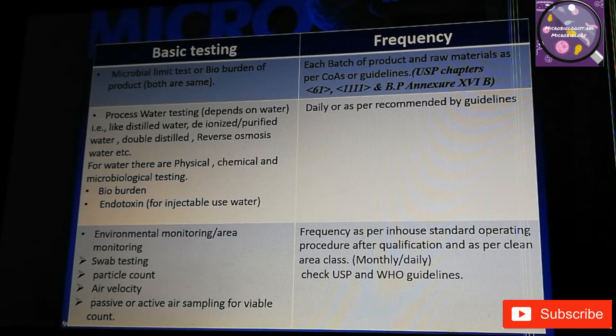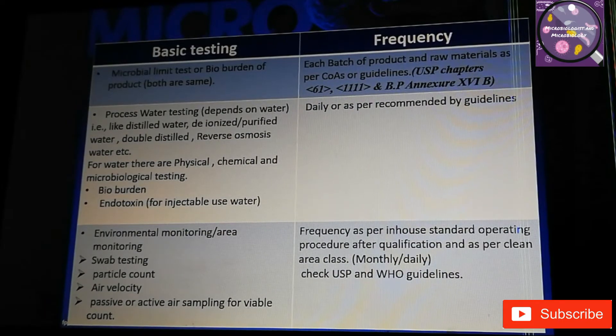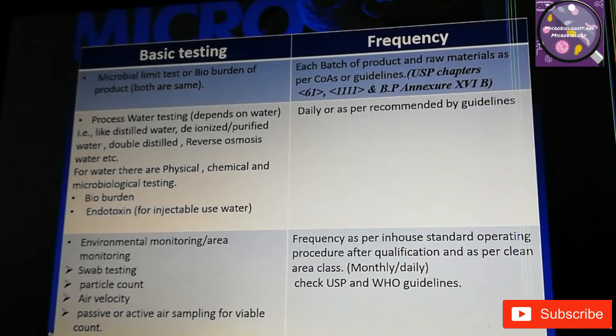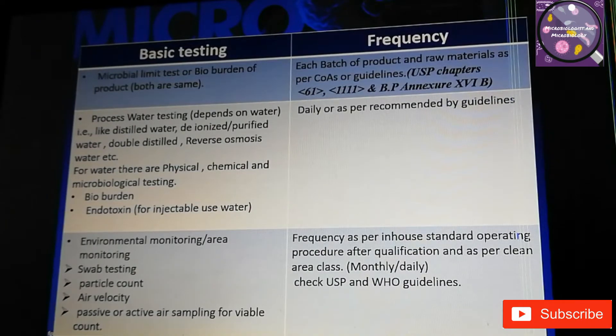You can set the frequency yourself as per the validation of your area. In pharmaceuticals there are cleanliness classes: Class A, B, C, and D. For aseptic areas we use Class A and B, and Class C and D are non-aseptic areas. The frequency depends on the class — sterile room areas require almost daily examination, while non-aseptic areas require monthly examination of microbes, either viable or non-viable.